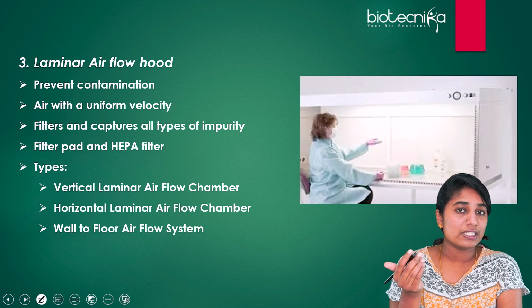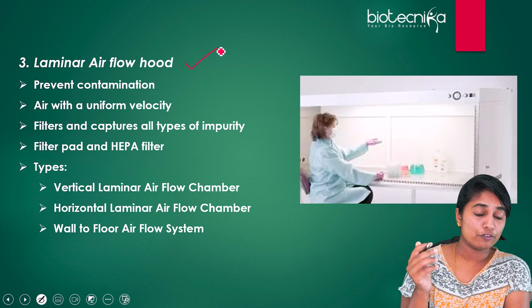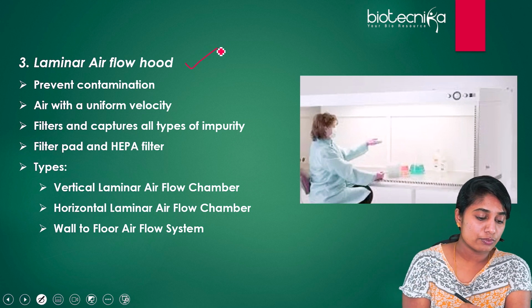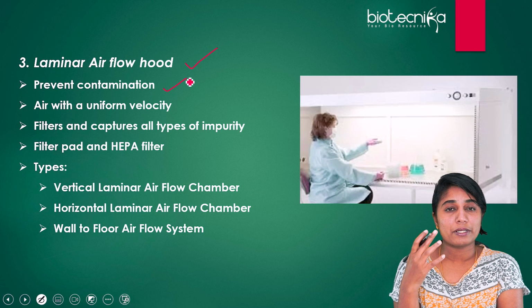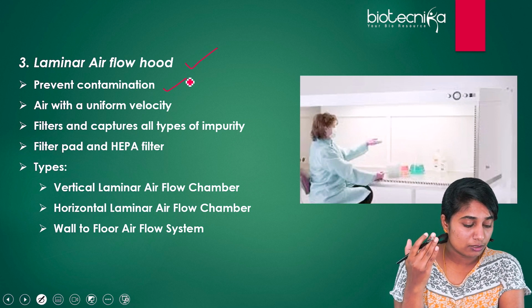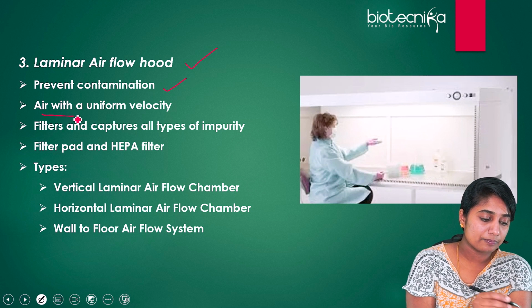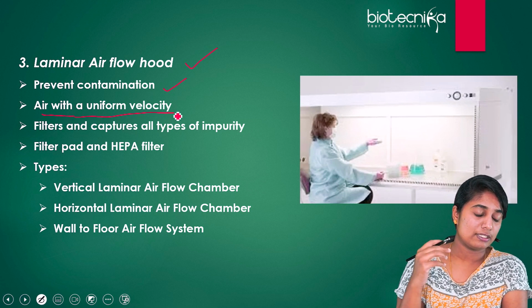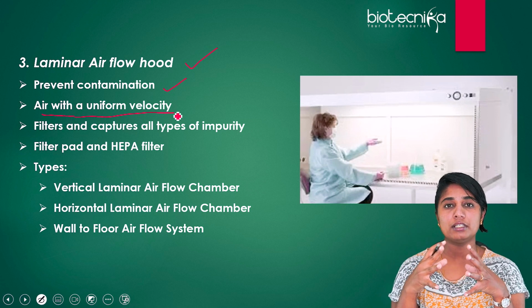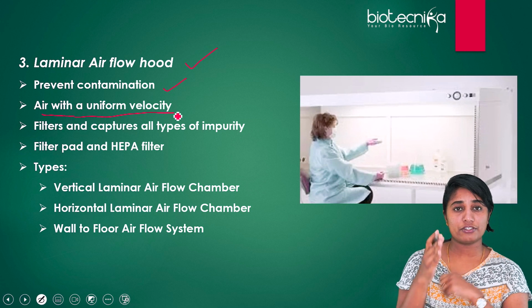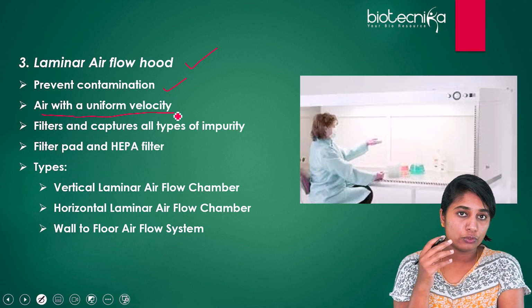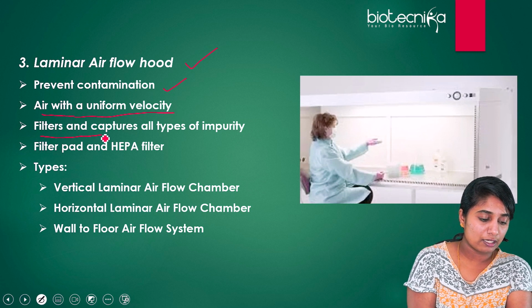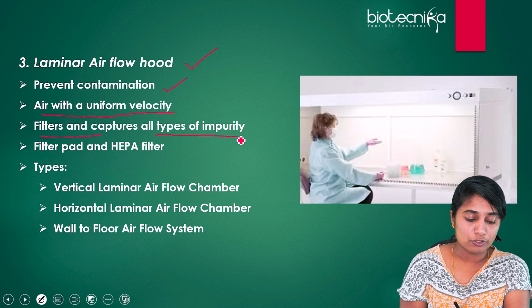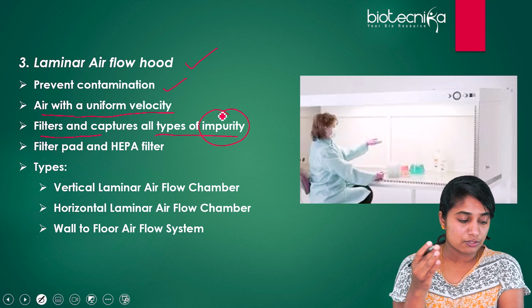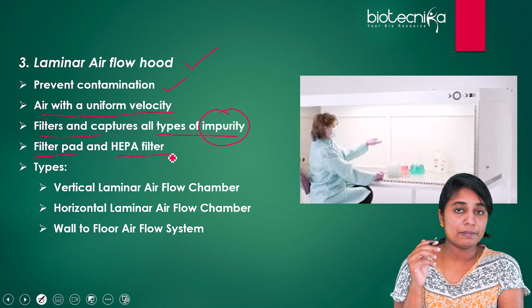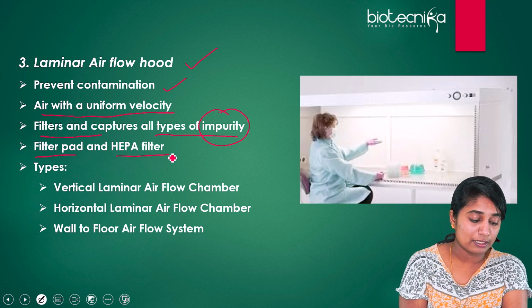The third instrument that we are going to see in microbiology is the laminar airflow hood. This hood is mainly used to prevent contamination at your workplace, especially when you're working with microbiological components. Here airflow is there with a uniform velocity. The air is always flowing through this particular hood with a uniform velocity, especially in straight lines, right? Before the air even enters this airflow hood, there are filters that have been placed to capture all types of impurities. Now, what are these filters that are used? One is a filter pad and one more is a HEPA filter. That's nothing but high efficiency particulate air filter.